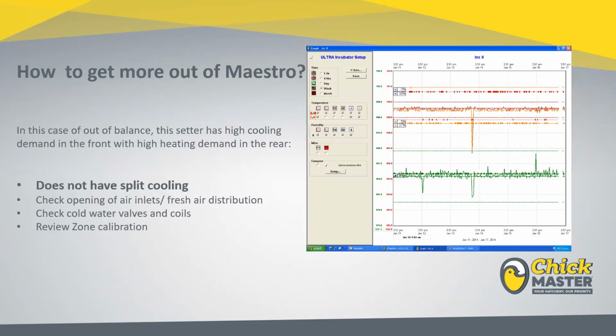Here's another case of an out of balance machine. In this particular case, the setter has high cooling demand in the front zone and high heating demand in the rear. So it's almost the opposite of the last machine. Again, one thing to point out on this machine that's a little bit different is that it does not have split cooling. So in other words, when the cooling functions, it's going to cool the rear of the machine first, but it'll cool the entire machine. So this could be a situation where we're not getting enough fresh air in the front zone, driving the cooling demand in the front, and that cooling demand in the front is overcooling the rear.